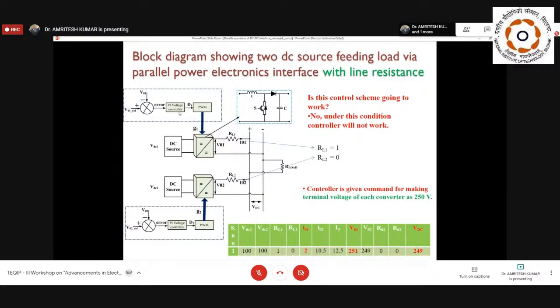If again with the same conventional control we try to maintain the terminal voltages V01 and V02 at 250 volt, okay, so suppose for converter 2 I'm trying to maintain this V02 at 250 volt and this line resistance is 0, then what is going to be the common DC link voltage? Obviously there is no line resistance, so V02 is going to be equal to VDC, fine. So if it is 250 volt, then again 250 volt is going to be the common DC link.